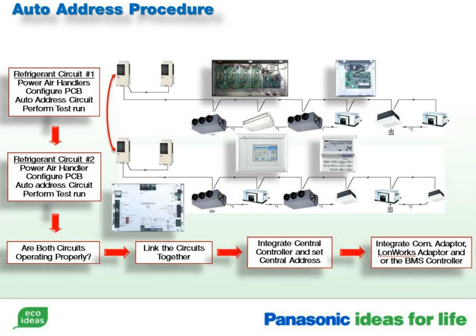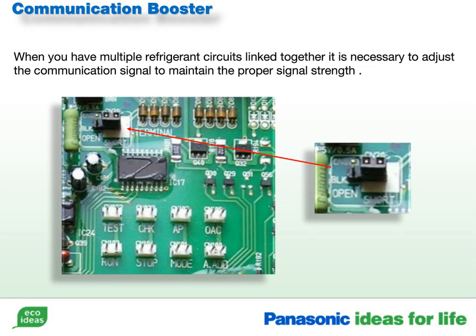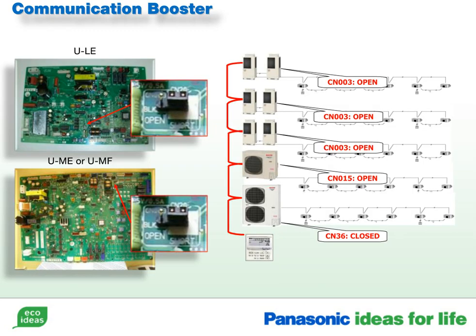If your job has a controls device such as a LonWorks adapter or a BMS controller, introduce it into the SNET last. When you have multiple refrigerant circuits linked together, it is necessary to adjust the communication signal to maintain the proper signal strength over the SNET. As shown in this example, one condenser of the 5 refrigerant circuits will need to be in the closed position. The remaining condensers should be placed into the open position. This also includes PACI units that may be present on the SNET.